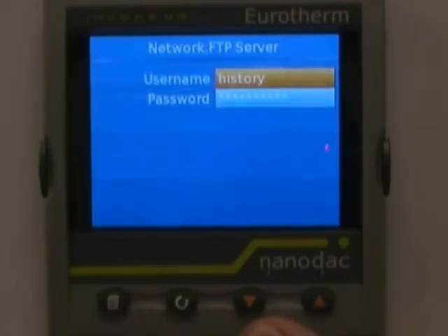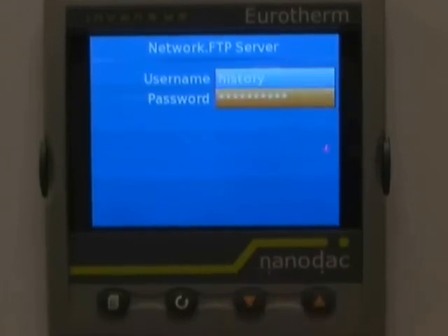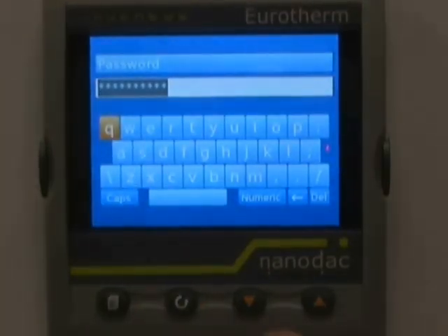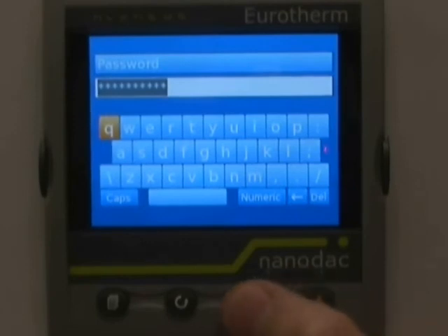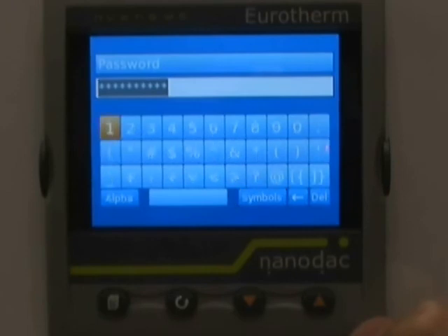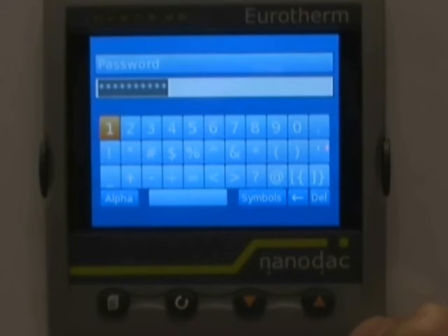We do not want to change the username from History — we just want to change the password. So we hit the down arrow to highlight Password and hit the scroll key once. Again we want the numeric keyboard, so we hit the left arrow three times to highlight Numeric and hit the scroll key once to change the keyboard to numeric. We'll use the common password of 100.